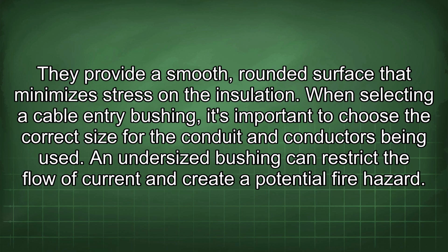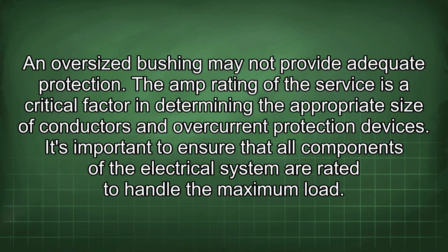When selecting a cable entry bushing, it's important to choose the correct size for the conduit and conductors being used. An undersized bushing can restrict the flow of current and create a potential fire hazard. An oversized bushing may not provide adequate protection. The amp rating of the service is a critical factor in determining the appropriate size of conductors and overcurrent protection devices. It's important to ensure that all components of the electrical system are rated to handle the maximum load.